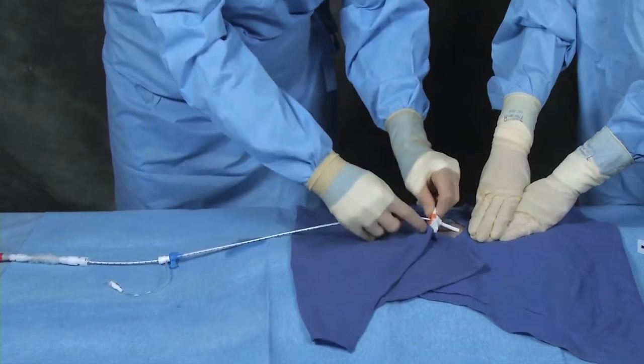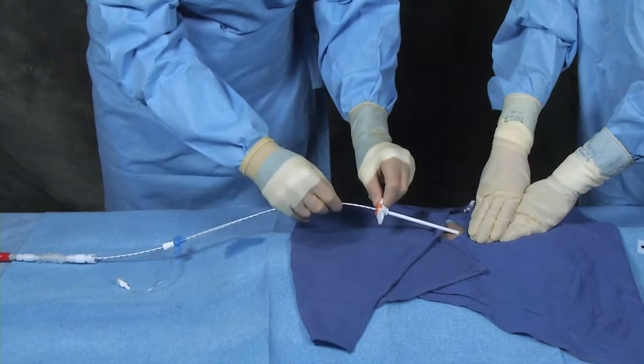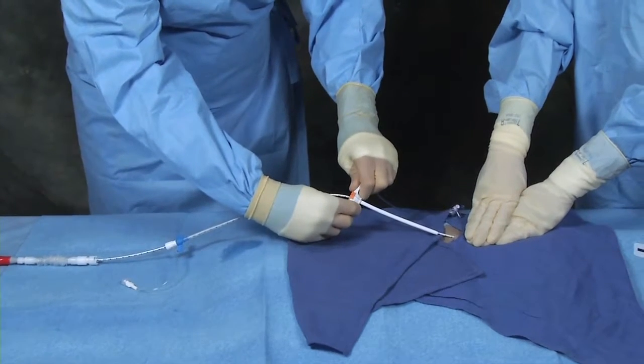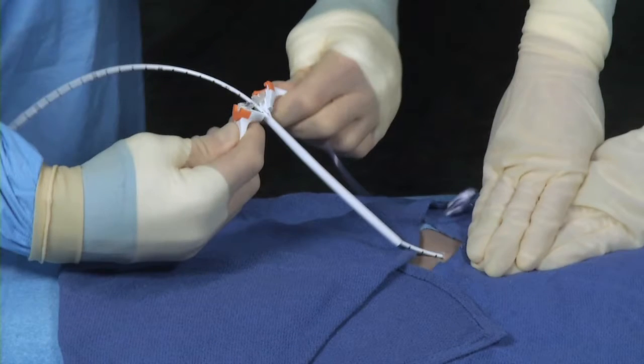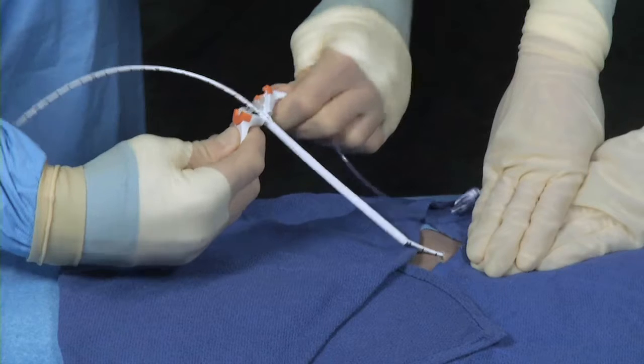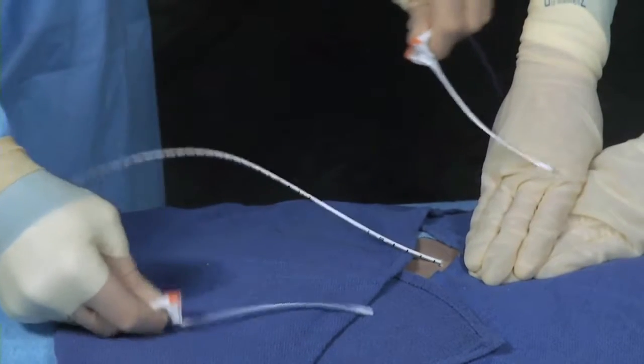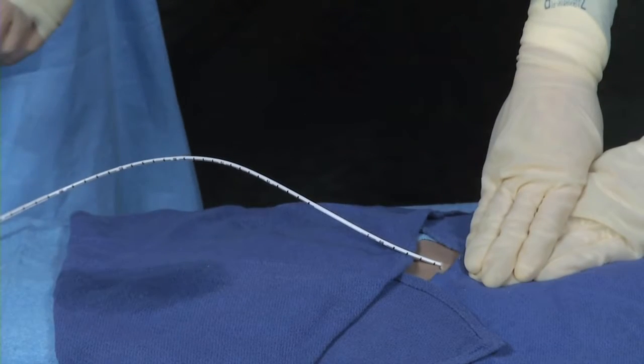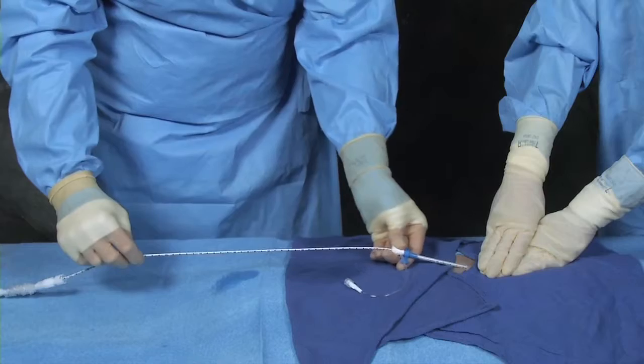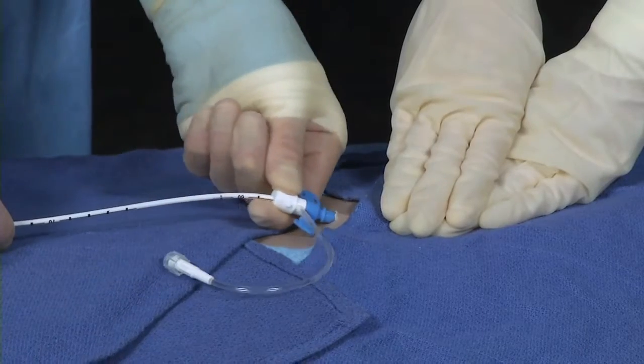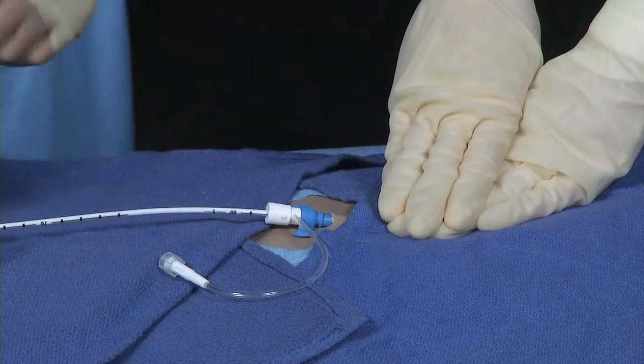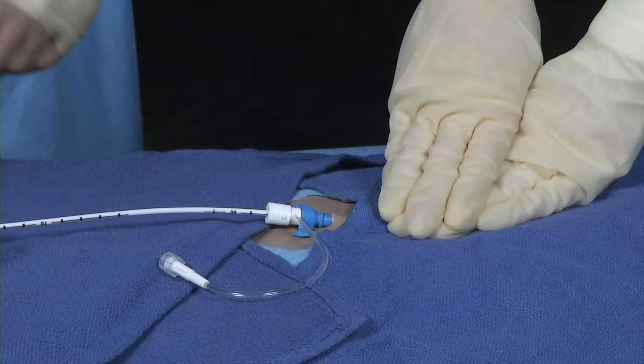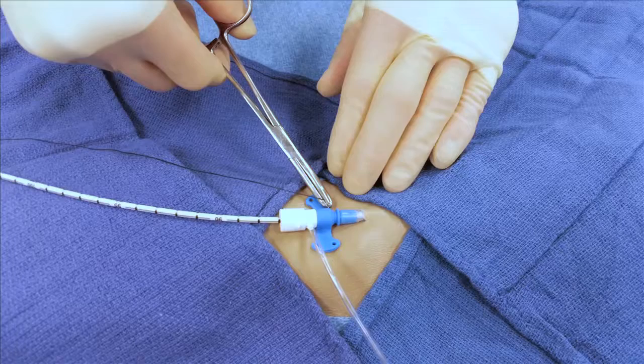Remove the peel-away introducer completely from the artery and skin, drawing it over the catheter shaft and applying more pressure to maintain hemostasis. Grasp the two wings and bend forward until the valve assembly comes apart. Continue to peel the two wings until the introducer is completely separated from the catheter shaft. Slide the repositioning sheath over the catheter shaft and advance it into the artery to the blue suture pads or until hemostasis is achieved. Secure the repositioning unit to the patient by suturing the blue suture pads to the skin or by applying a StatLock stabilization device.